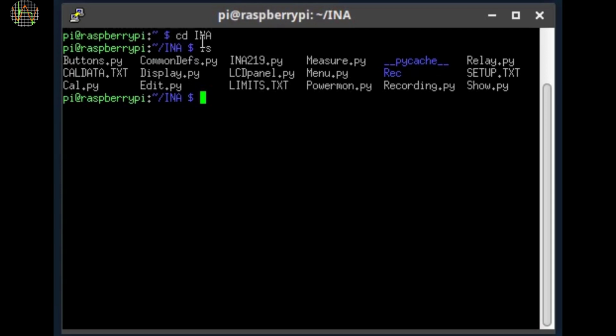At the moment, there's only very crude error handling on reading these files, and most importantly, this means if something in the format has changed with a new software version, you must manually delete the old setup text before starting the new software for the first time, or the program will most likely crash. In principle, the same is true for the limits file, but that one has been stable for quite some time now, and I don't expect many changes that could affect the file format.